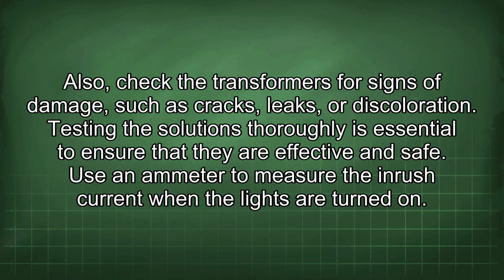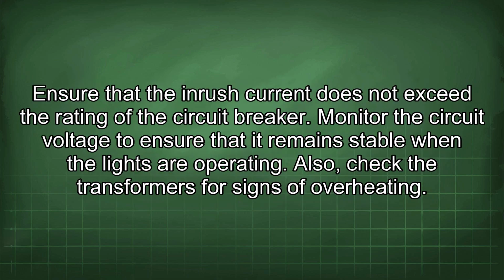Testing the solutions thoroughly is essential to ensure that they are effective and safe. Use an ammeter to measure the inrush current when the lights are turned on. Ensure that the inrush current does not exceed the rating of the circuit breaker. Monitor the circuit voltage to ensure that it remains stable when the lights are operating. Also, check the transformers for signs of overheating.